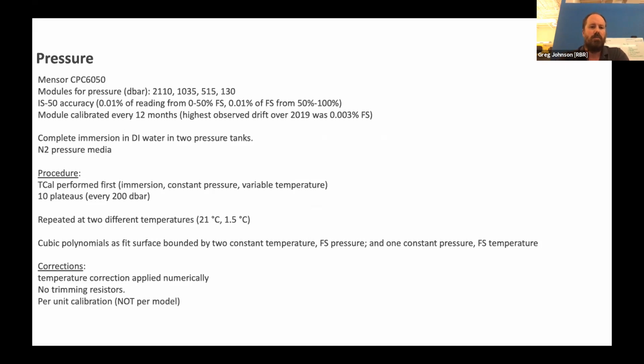And at the moment, for instance, for a 2000 dbar calibration, we'd use the Mensor CPC6050 that we have. It has 4 different quartz-based pressure references inside, so we actually switch the range automatically as we're ramping up. We start at 10 dbar, we go up 100, 200, so on, 2, 4, 6, 8, up to about 2000 dbar. Different references are used for each of those, and they have this very slightly mind-blowing way of defining accuracy. It's called IS50.